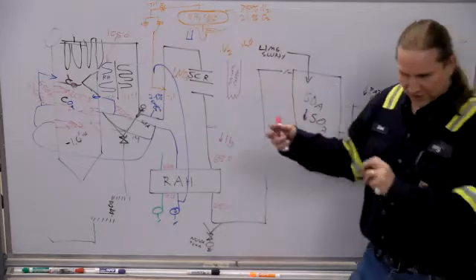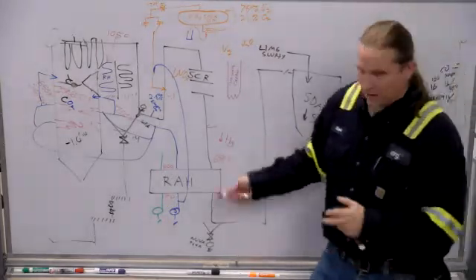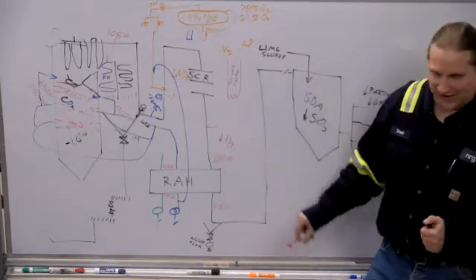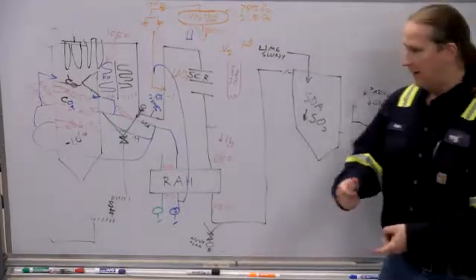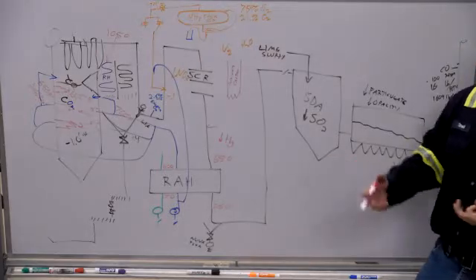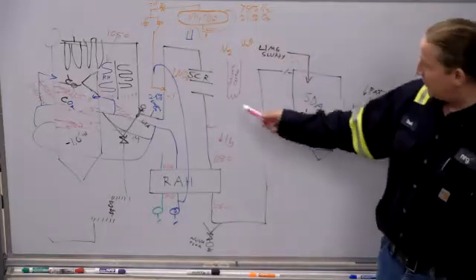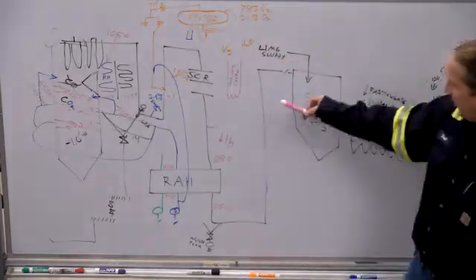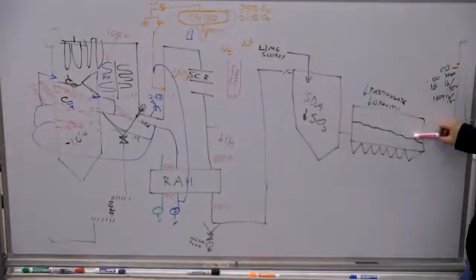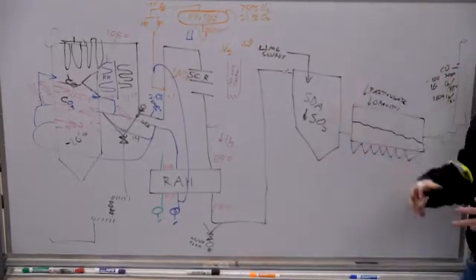The carbon is something that has a lot of surface area to it, and it will bond with all the stuff that we don't want in the flue gas. Mercury is the one that there actually has a limit for, that is actually being controlled. But if there is lead, or iron, or whatever else they dug up with the coal, that might get in the air and might be poisonous, this carbon is absorbing all of it. And that carbon blows into the flue gas, and then it builds up on the sides of the bags, and that's where the actual reaction is mostly happening, when the flue gas is getting pulled through the bags.